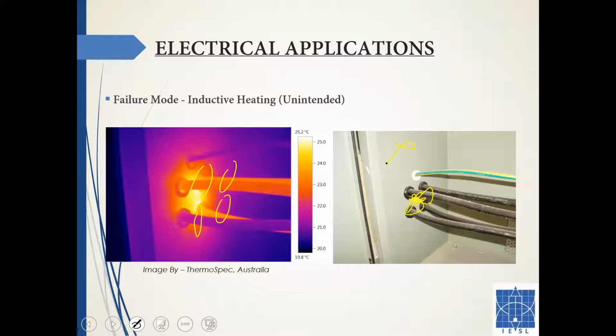So what happens is you have a stray current going on this plate, and from the copper loss, I squared R is increasing. I have seen cases where this particular heat generated from the eddy currents from the inductive heating wears off the paint, and it gets really hot, up to beyond 100 degrees easily given the high currents.